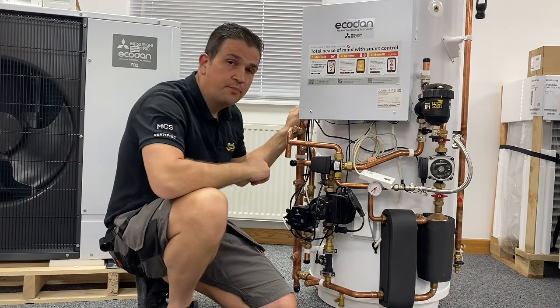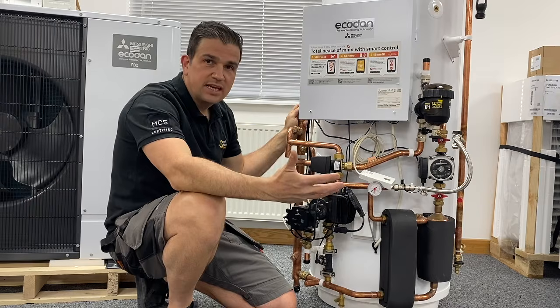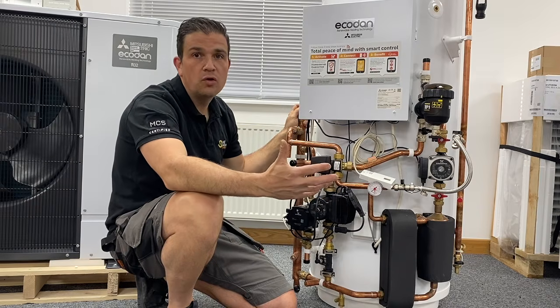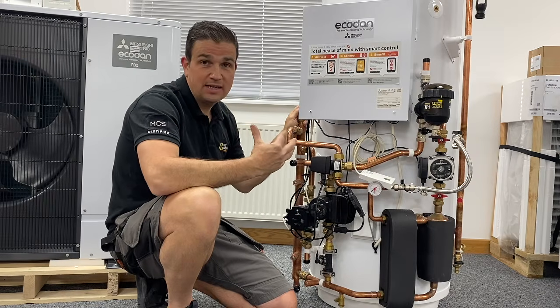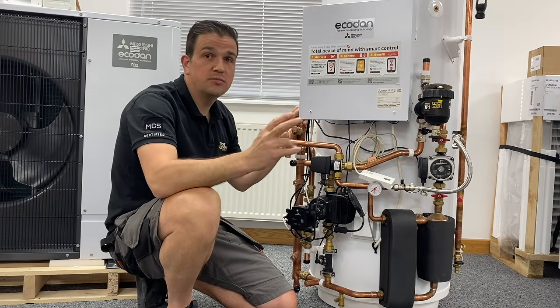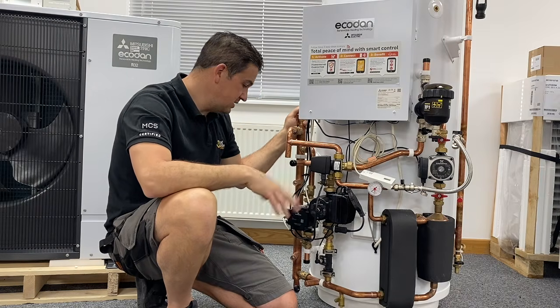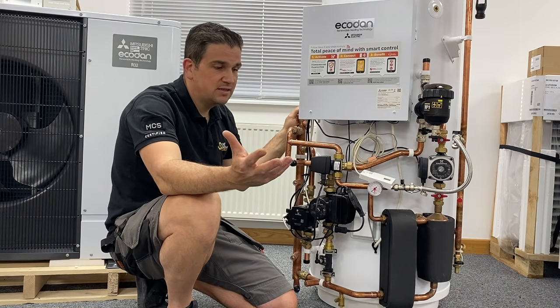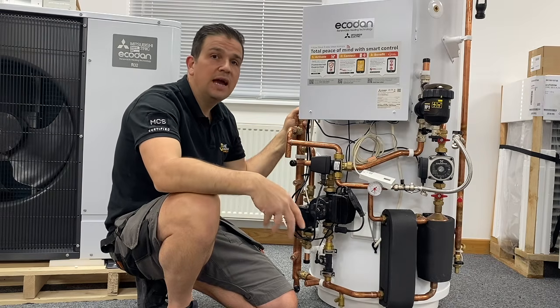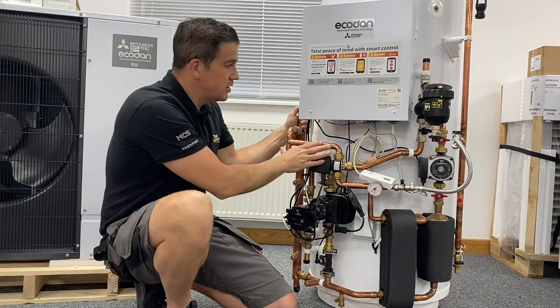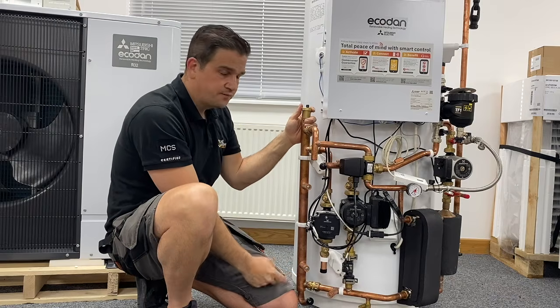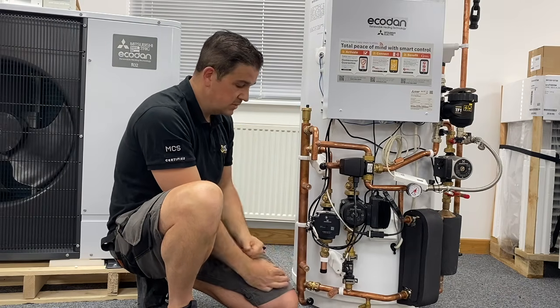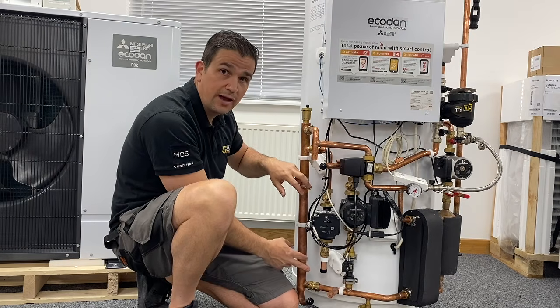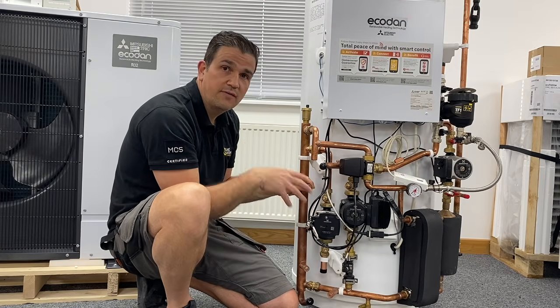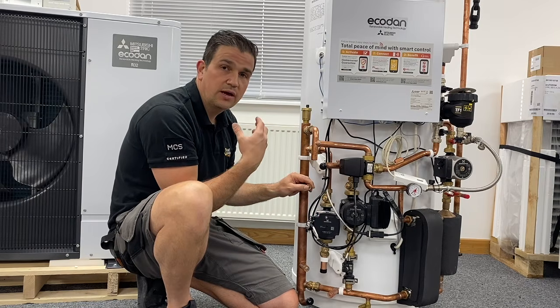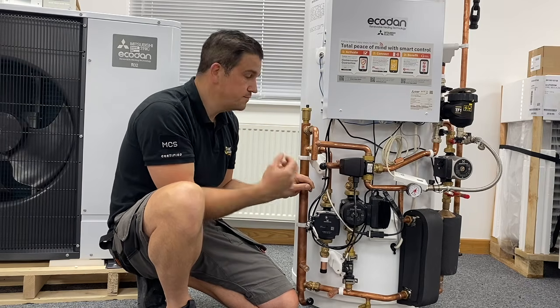Okay, so the pre-plumbed cylinder. This comes with most of the ancillaries which you are going to require for your heating system. Generally, the way we rig these up, we can put them on up to 2 zones. What that means is that, as I've said in many instances, you might have downstairs, which has got underfloor heating, and your upstairs are radiators. Now, on the side of this heat pump, we've got what we call a low loss header. This helps with the hydraulics of the system, and enables us to put connections on for another flow and a return. Additional to this, we would have to add a pump, for example, to circulate the water to said zone.